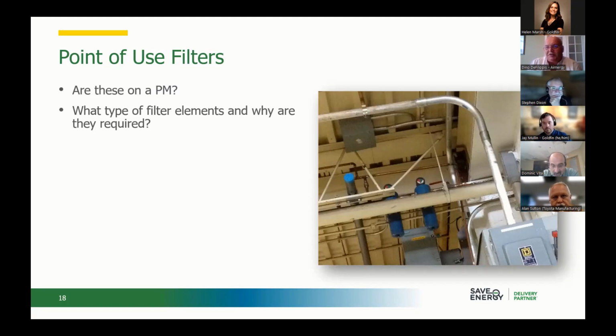The reason I put this out is that very seldom does the maintenance team ever know that there are filters sitting in the ceiling, and they're not on a PM program. And when they start running into problems with pressure and the machines aren't cycling properly, the first thing they do is they go increase the pressure on the compressors. Yes, it solved it, but here's the issue.